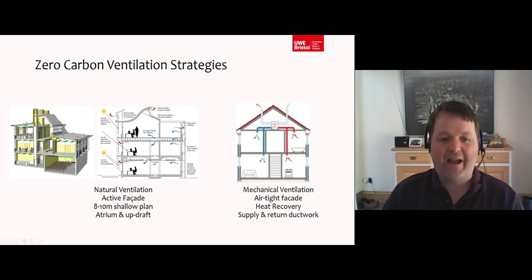heat recovery. So natural ventilation is the type of technology we use in our block, and it usually has a very active facade, so windows on the edges of the building that automatically open and close, or louvers which automatically open and close, and then some way of drawing air up through your building. It's using two natural forces, one of wind pressure at the sides of the building, but also of the hot air rising up through the building. And in fact, in the worst case scenario, in the middle of the summer, you have to assume there's no wind, so you're actually designing for just the buoyancy factor of pulling enough air through this building just by the fact that hot air is rising in that worst case scenario.